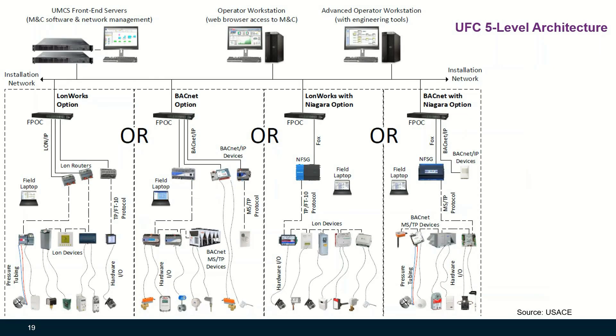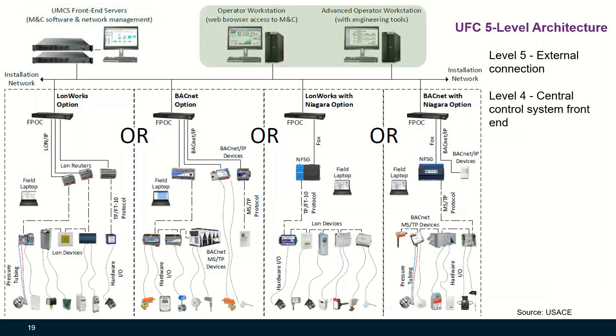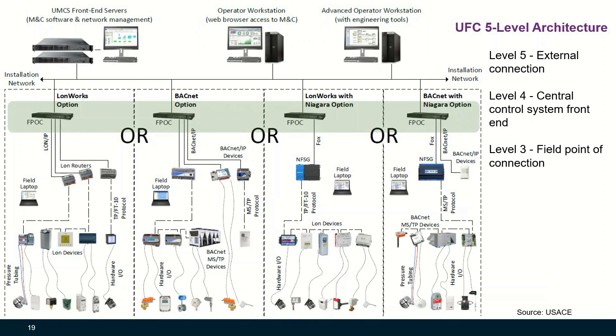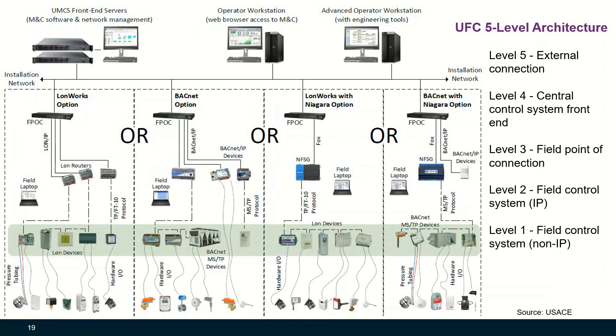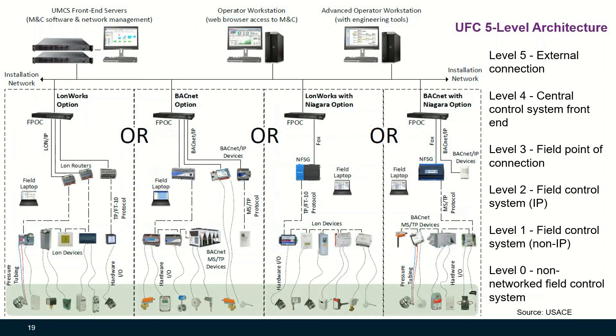In the Unified Facility Criteria (UFC), a five-level control system architecture is defined. Level five is the external connection level. Level four is the central control system front-end, which includes operator workstations or advanced operator workstations. Level three is the field point of connection. Level two is the field control system IP network. Level one is the field control system non-IP network. There is also a level zero for non-networked field control systems.